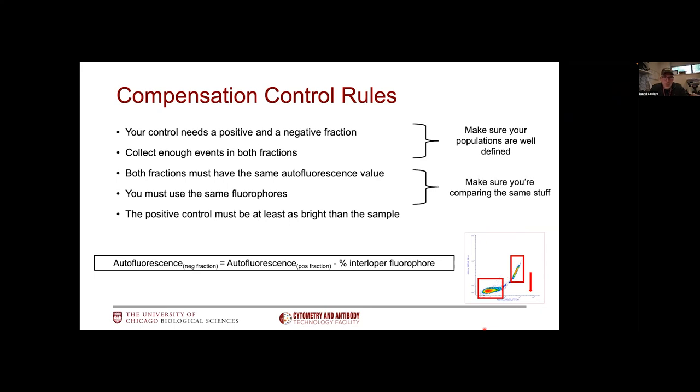The next two rules make sure that you're comparing the same stuff. The first one says both fractions must have the same autofluorescence value. This is fundamental if the goal is to subtract the percentage of a signal spilling into the wrong detector so that the autofluorescence of one fraction is equal to the autofluorescence of the positive fraction. Obviously, you want the autofluorescence to be the same to begin with.